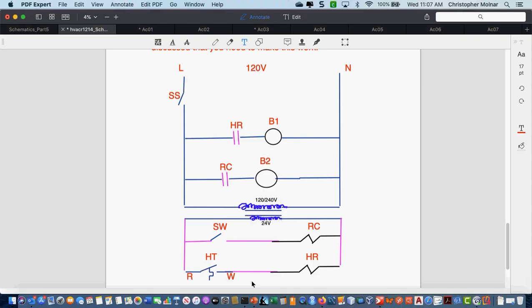Service switch is closed, provides power to the 120 volt primary of the transformer, which in turn allows the 24 volt side to get power. When the SW switch is closed, the RC coil is energized. RC contact closes and powers bulb 2. When the heating thermostat calls for heat, it closes R to W, powers the heat relay HR, which closes the contacts HR and powers B1.